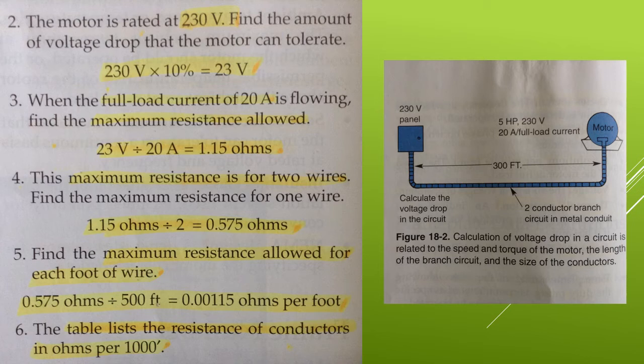Step 5, find the maximum resistance allowed for each foot of wire. In this case, we have 0.575 ohms divided by 500 feet, which gives us 0.00115 ohms per foot. So we're using a length of 500. Odd because the example shows 300, but that's what the text says, 500. We'll go with that for now.